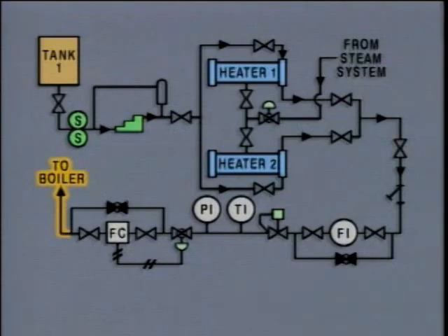Next is a pressure regulator, represented on the diagram by a symbol for a self-regulating valve. Then there is a local temperature indicator and a local pressure indicator. The next group of components includes a pneumatically actuated flow control valve connected to a flow controller. The controller and control valve make up an automatic system that monitors and controls the flow of oil to the boiler. The other valves are for isolating and bypassing the flow controller if necessary. From there, the oil is fed to the boiler.